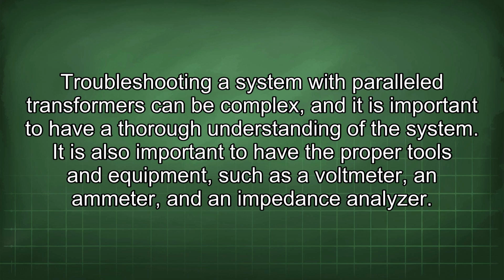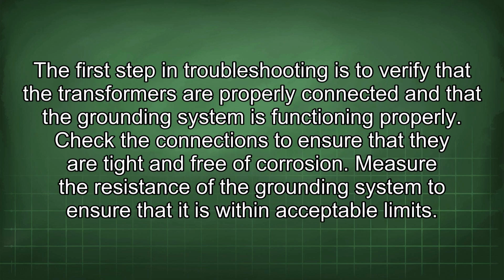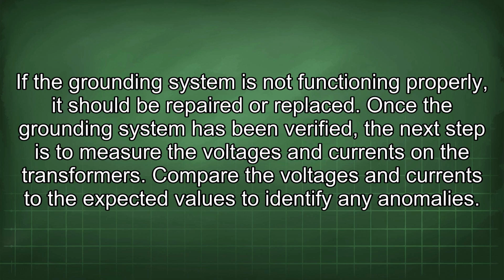Troubleshooting a system with parallel transformers can be complex, and it is important to have a thorough understanding of the system. It is also important to have the proper tools and equipment, such as a voltmeter, an ammeter, and an impedance analyzer. The first step in troubleshooting is to verify that the transformers are properly connected and that the grounding system is functioning properly. Check the connections to ensure that they are tight and free of corrosion. Measure the resistance of the grounding system to ensure that it is within acceptable limits. If the grounding system is not functioning properly, it should be repaired or replaced. Once the grounding system has been verified, the next step is to measure the voltages and currents on the transformers.